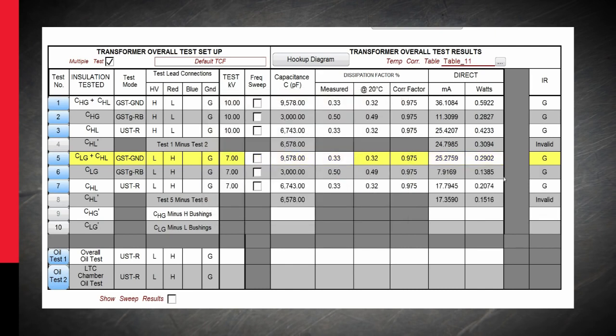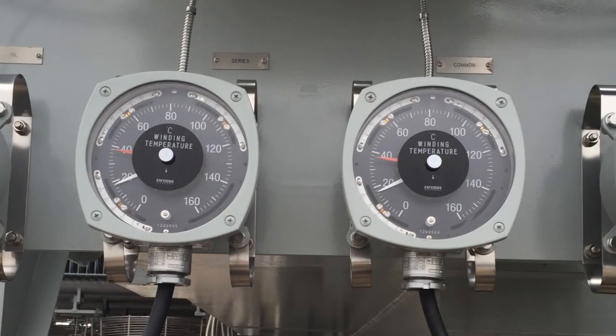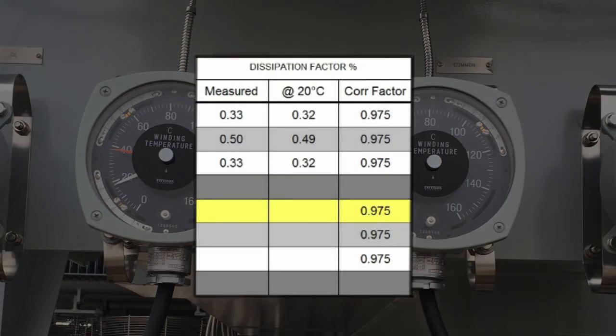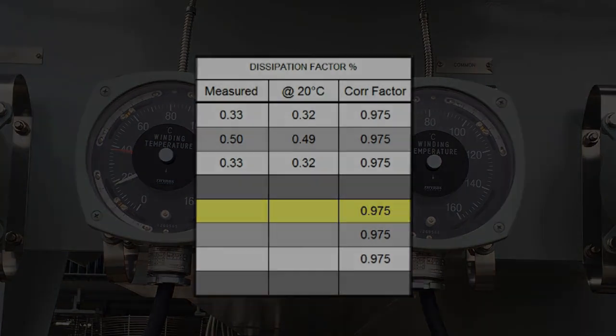Once we see the results are as expected, we can confirm good insulation condition of the main body of the transformer. For proper correction of results, we must input correct transformer oil temperature into nameplate info. Temperature can change results significantly, and so correct temperature is critical.